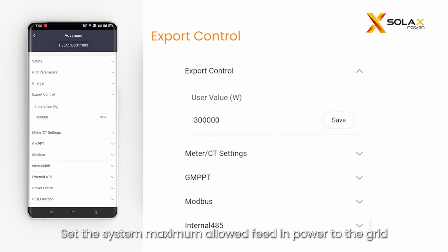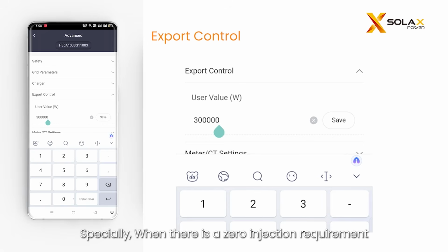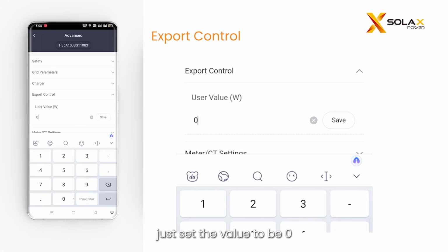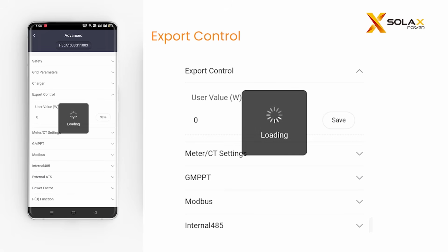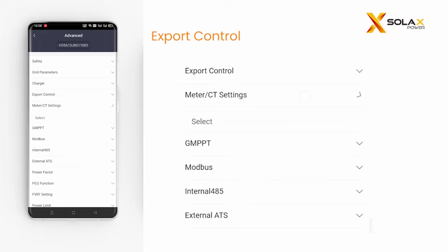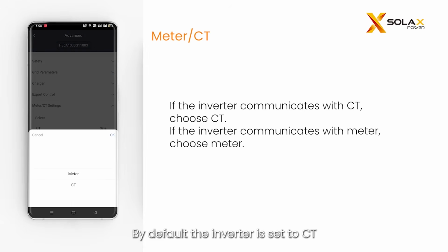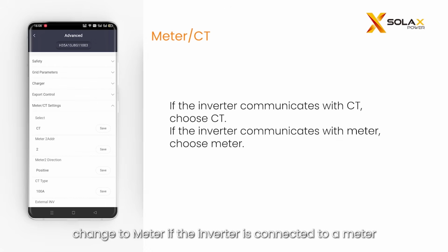Set the system maximum allowed feed-in power to the grid. Especially, when there is a zero injection requirement, just set the value to be 0. By default, the inverter is set to CT. Change to meter if the inverter is connected to a meter.